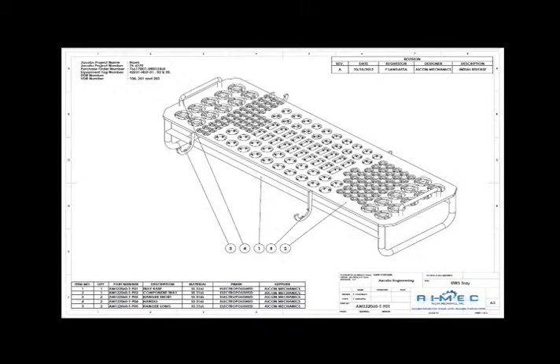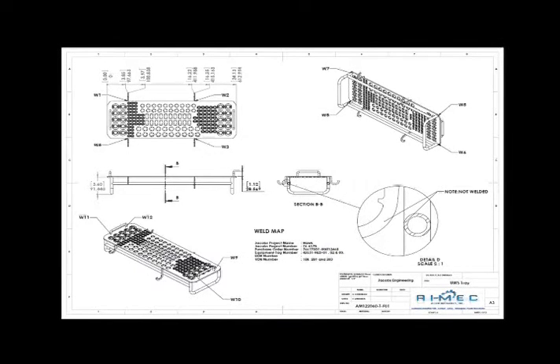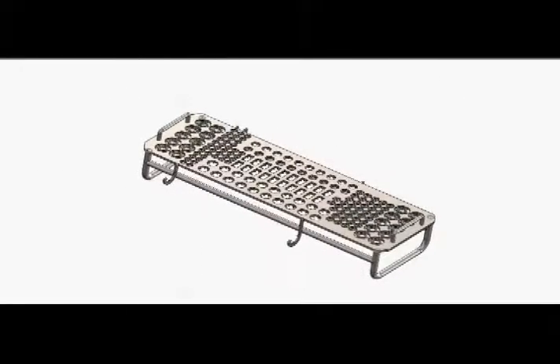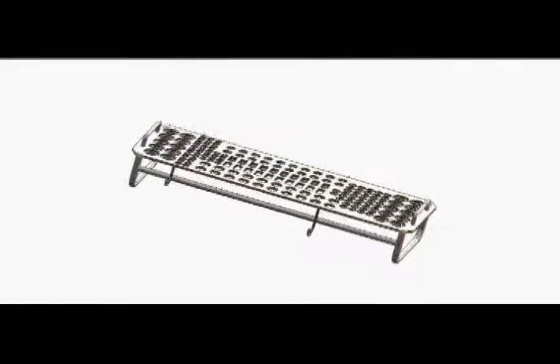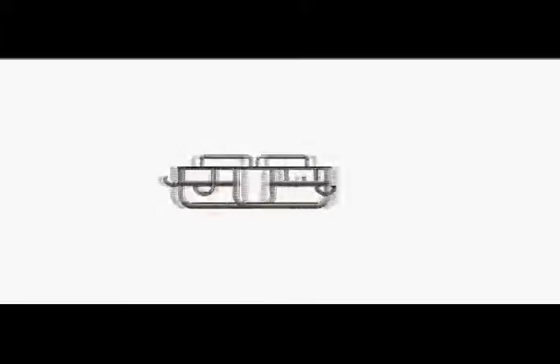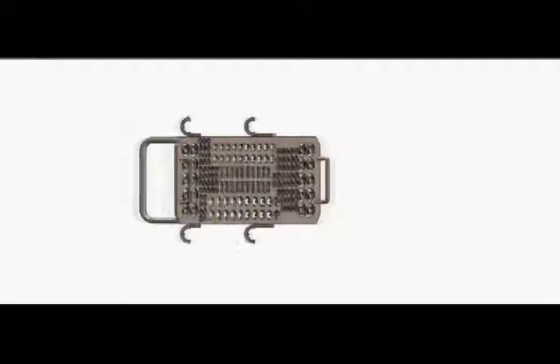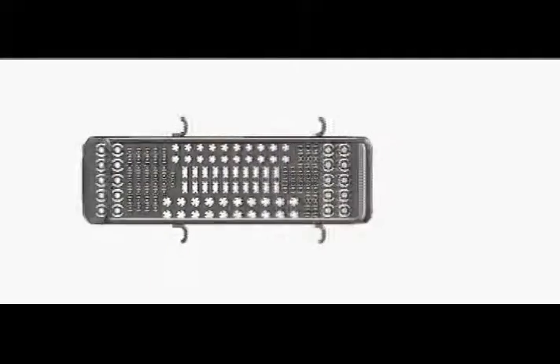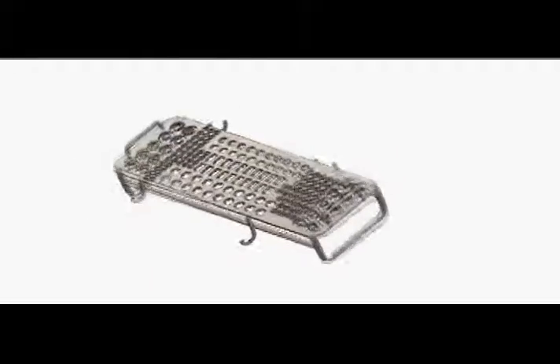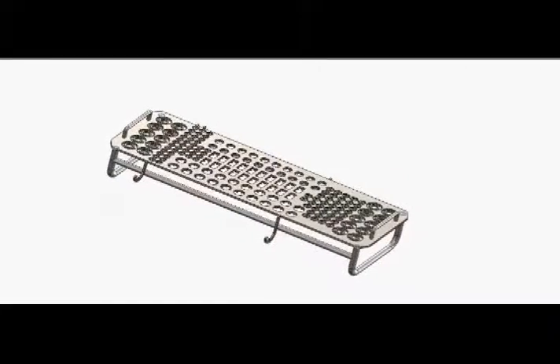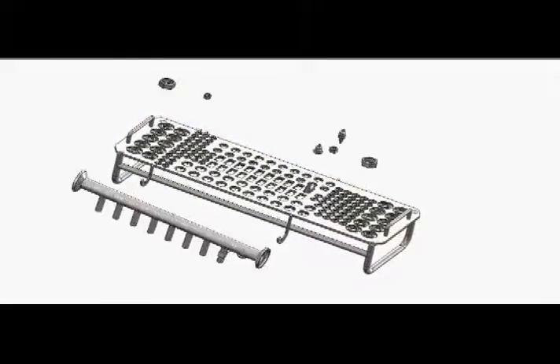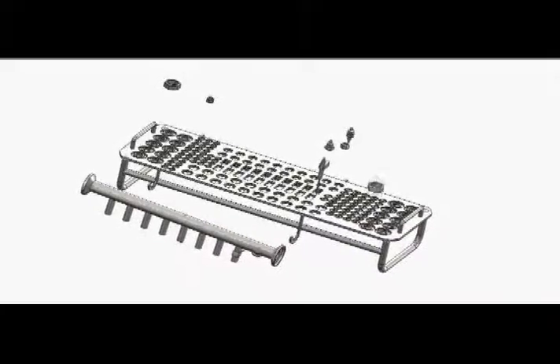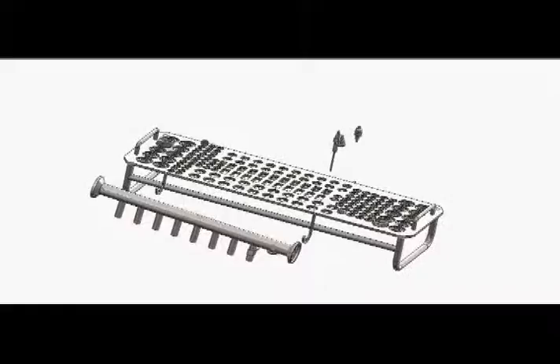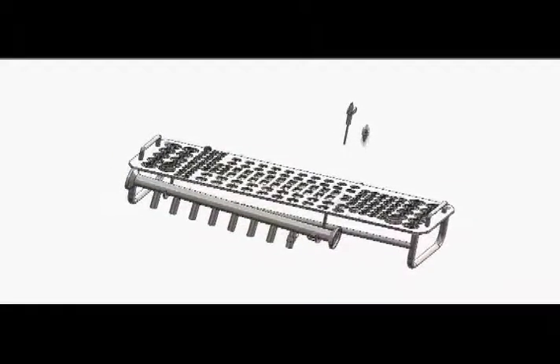So we came up with the following solution: a tray, completely made out of stainless steel 316L, capable of holding at least 24 sets of needles and peripheral equipment, with a maximum contact between parts and the cleaning or sterilization agent, easy to use, transport, clean, and capable of allowing a fast and robust accountability of parts. The manufacturing process consisted of a milling-based CNC approach, with all welds made under a sanitary protocol and all surfaces polished to Ra less than 15 nanometers.